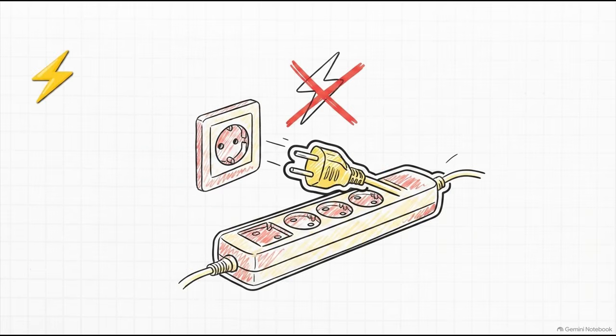And this brings us to the ultimate failsafe. Utilizing universal agents, the software maps every single server to a specific electrical outlet on an integrated Schneider Electric PDU. If the CDU detects an inconsistent temperature ratio or a flow rate issue, which basically indicates a severe anomaly in that closed loop, the software bypasses the server entirely.